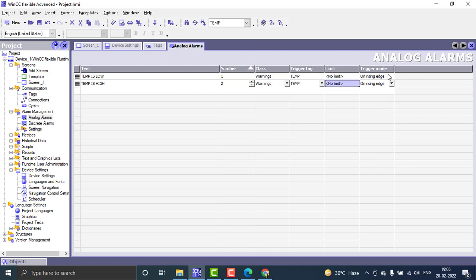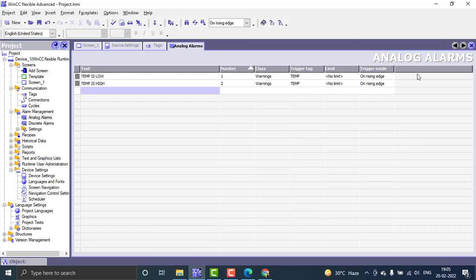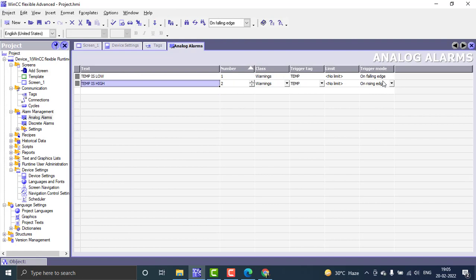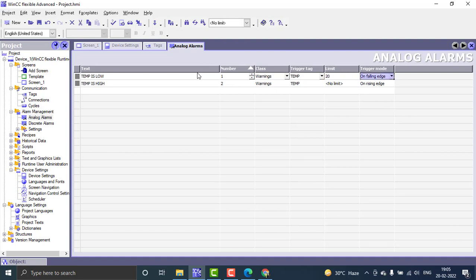There are two types of trigger modes: rising edge and falling edge. For the low temperature alarm, I'm using the falling edge — that means when the temperature drops below 20, it triggers the temperature low alarm. And if the temperature rises above 80 on the rising edge, that triggers the temperature high alarm.